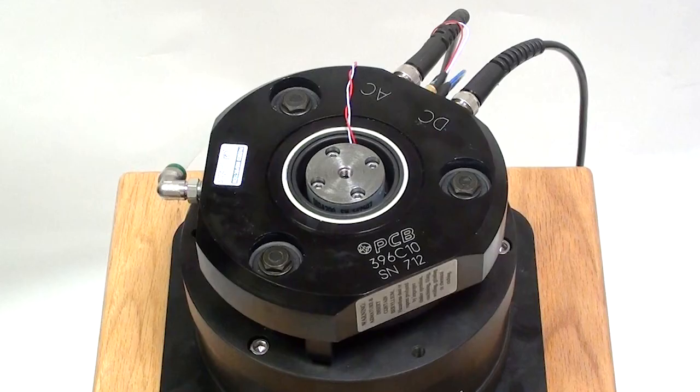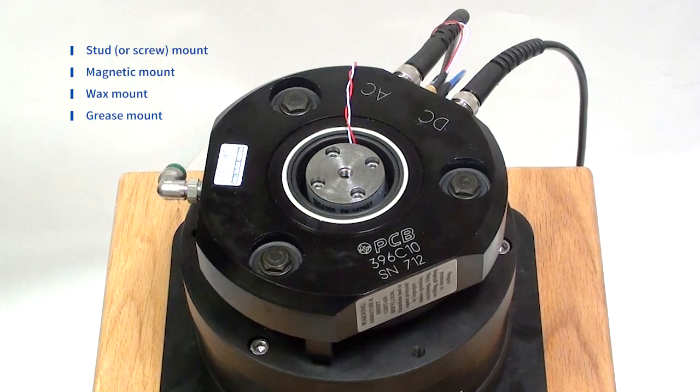In summary, choosing your preferred calibration mounting method, whether it is the same as will be used during testing, or rather the best possible technique to reproduce factory performance, offers you the data necessary to ensure confidence in the measurements from your next test.